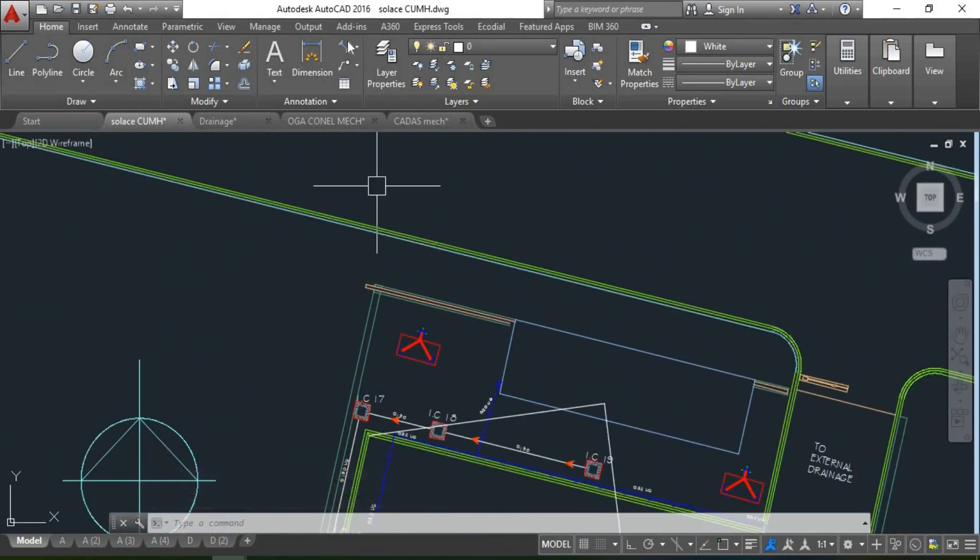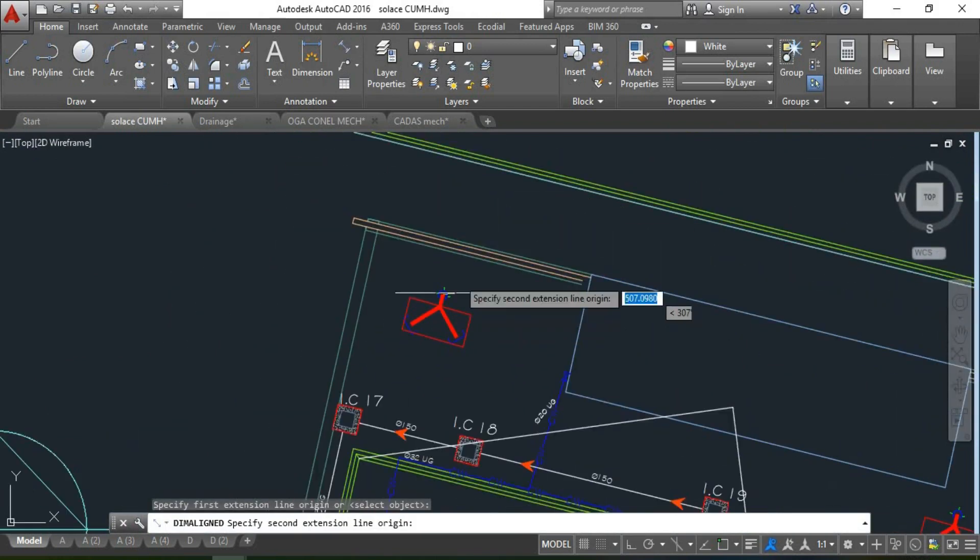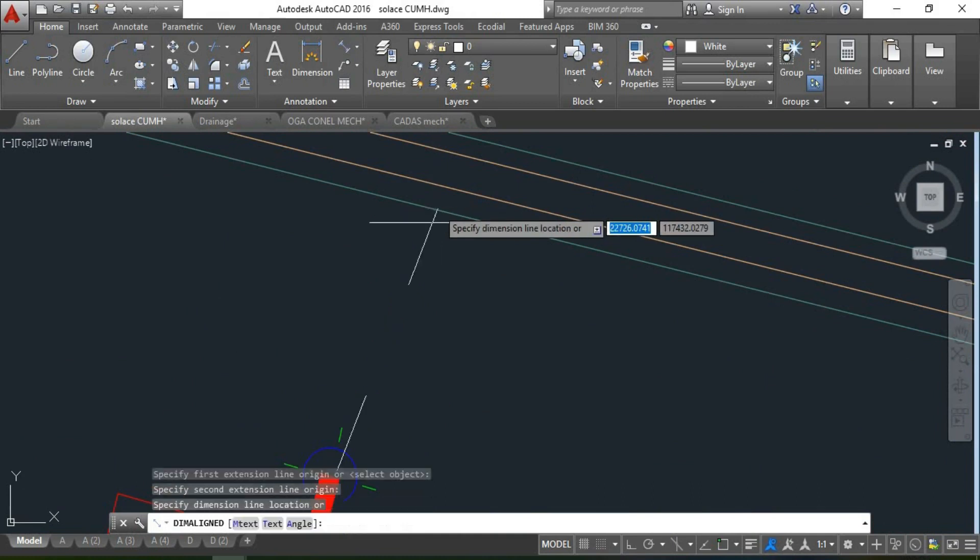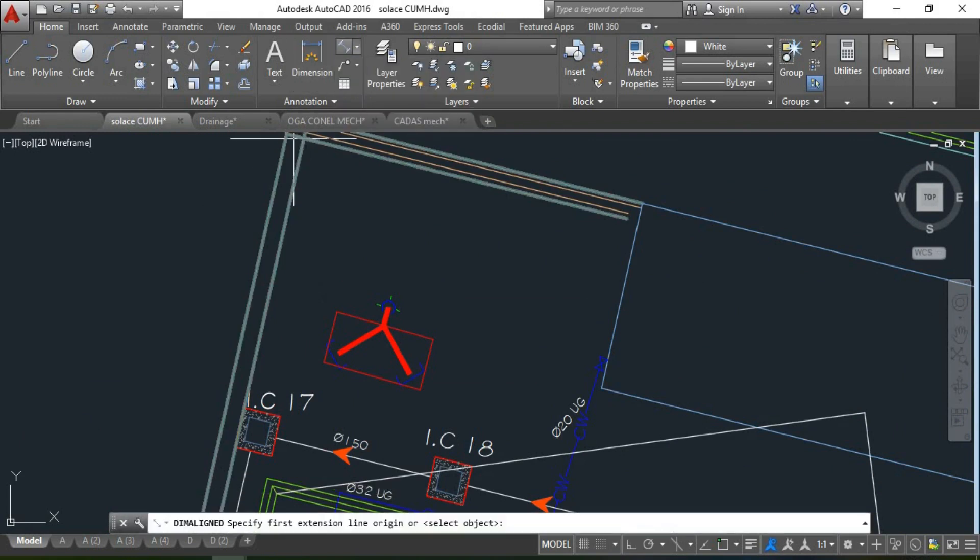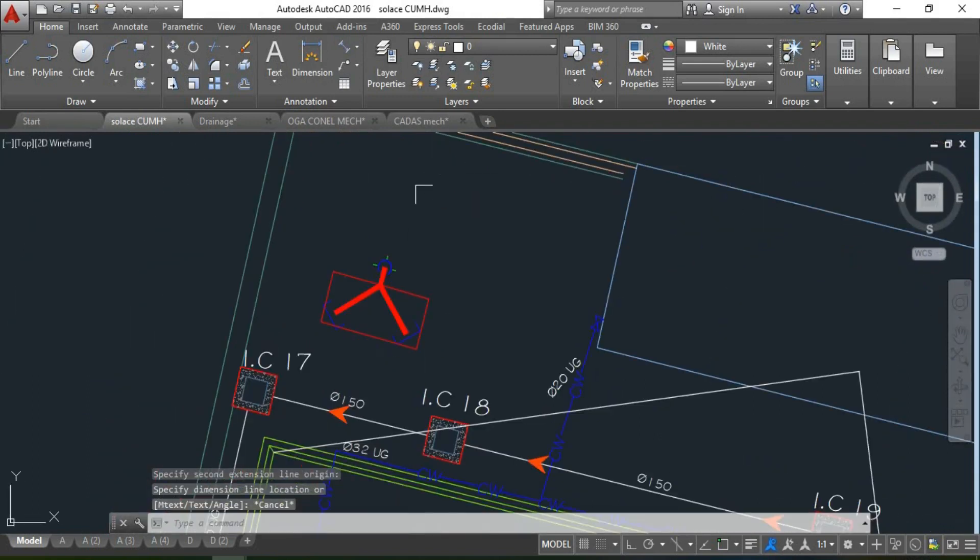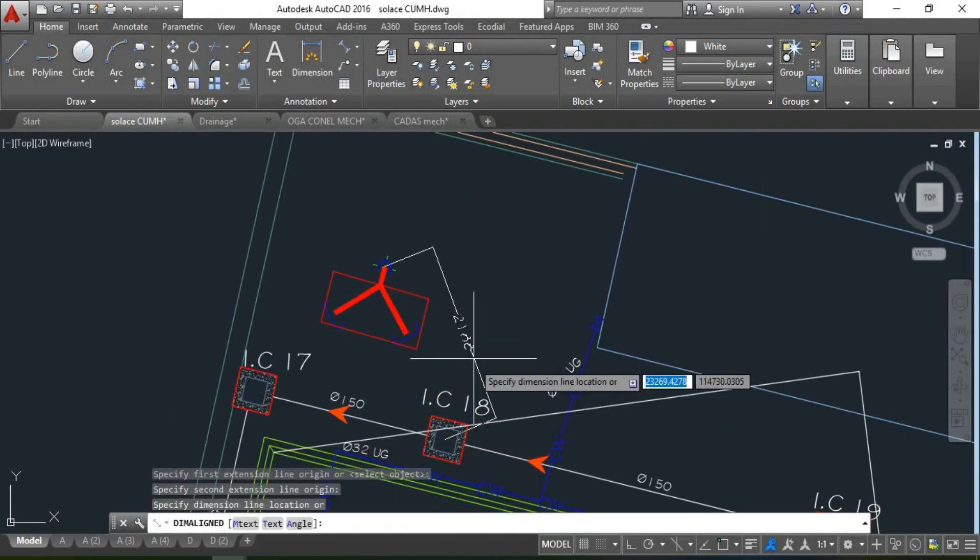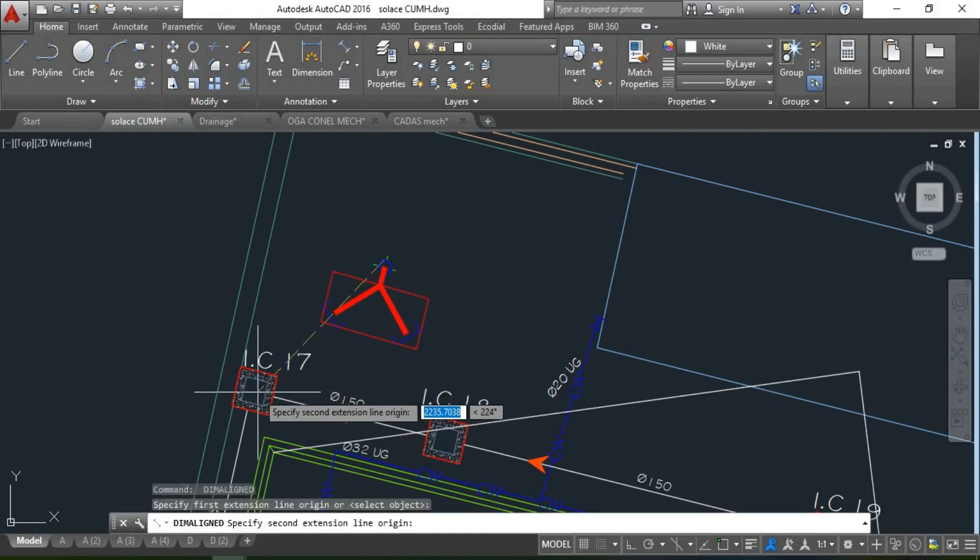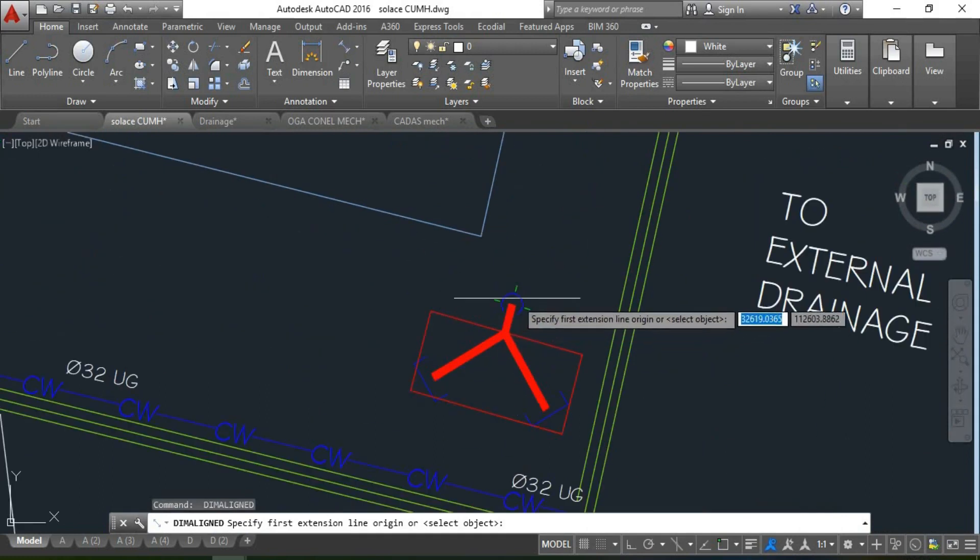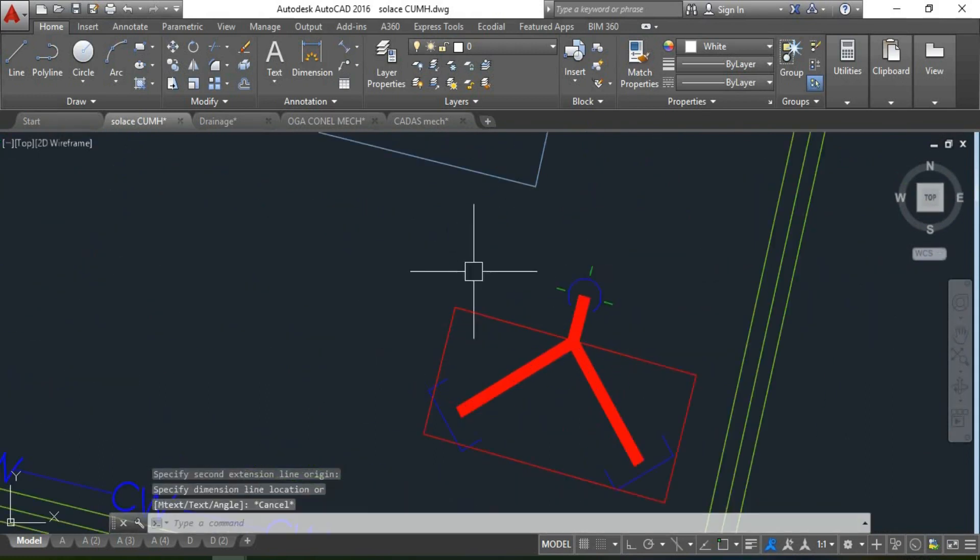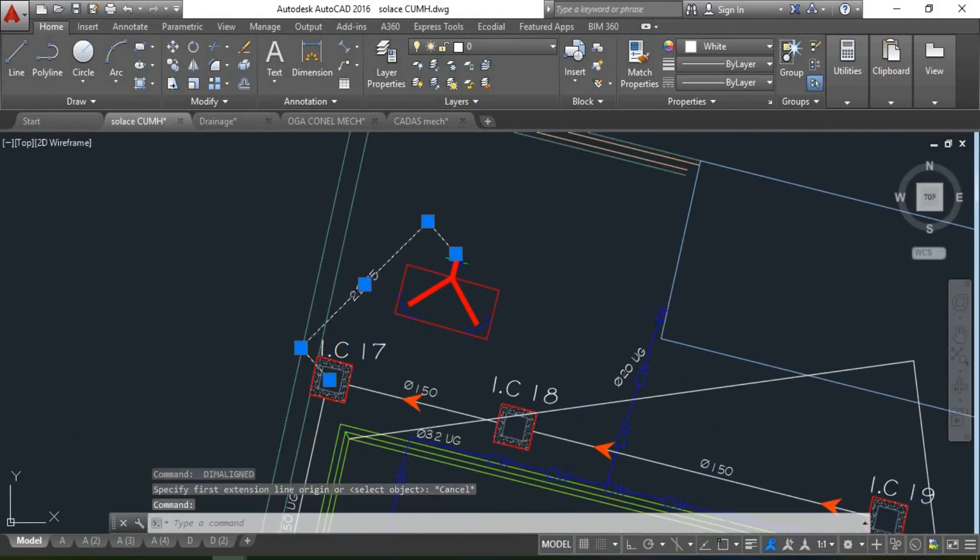Considering NFPA again, minimum of 1.5 meter from any obstruction. We still need to move it very close here. Let's check. We are good to go. This is actually another best fit position. Let's consider this - we have our gatehouse very close which implies it doesn't work here. So this is another best fit position.